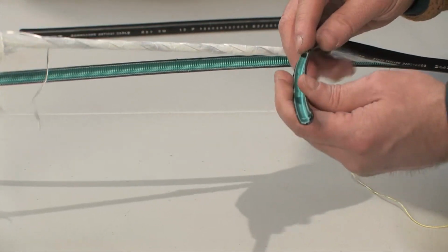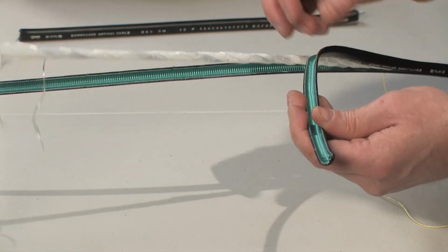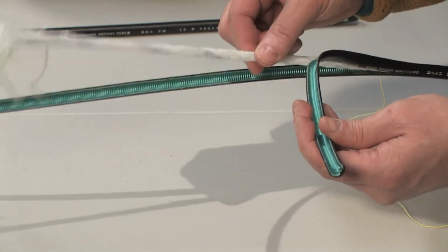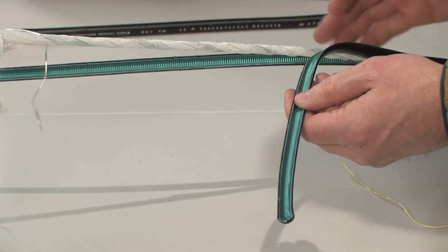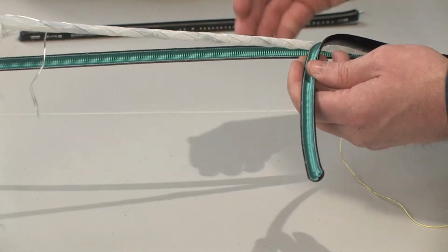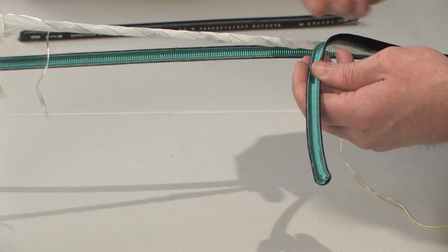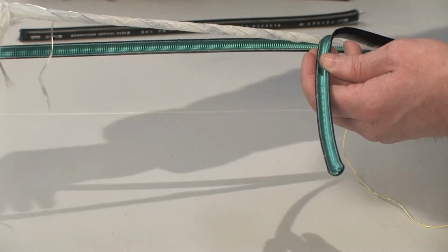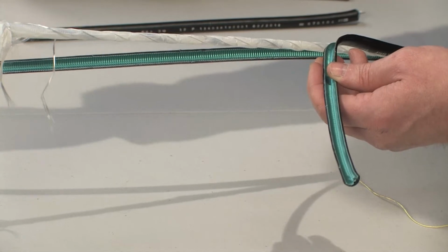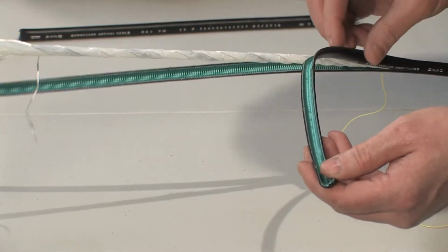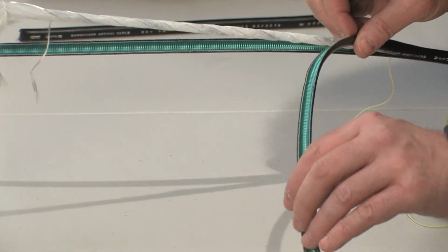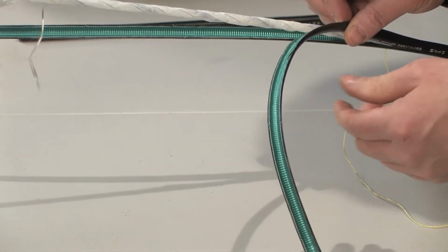If they bond this off, lightning will then pass along the bond instead of going through the cable and into the fiber itself. If it's not properly bonded at each end of the cable, then generally what would happen is the lightning will strike and it'll burn through the side of the cable, burning multiple holes throughout the cable until it finds that bond point and then would exit outside of the cable. It's very important that you understand that when we get to building out the fiber cases.